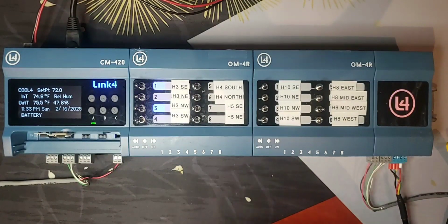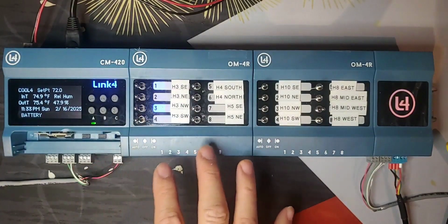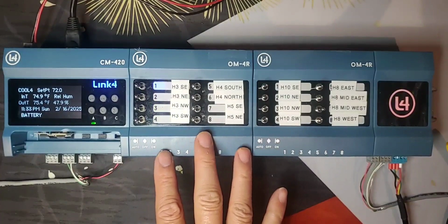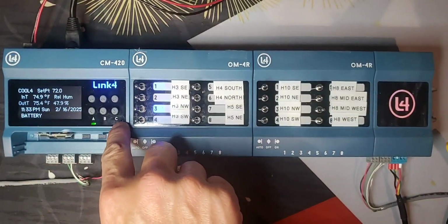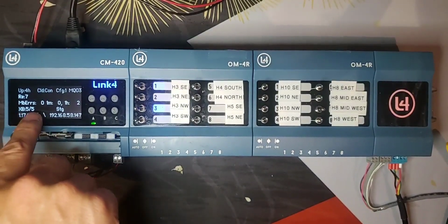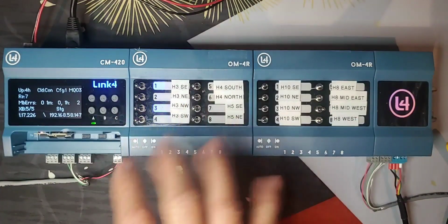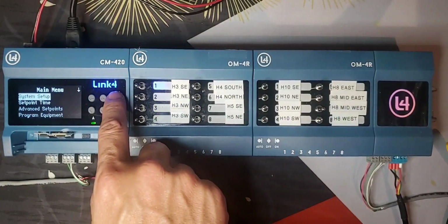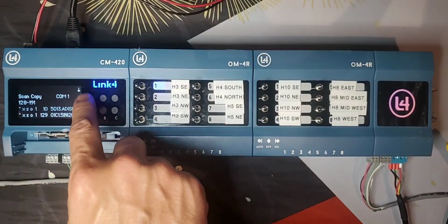So typically, if you see it go solid, that means somebody is communicating, is holding on to the line. Then the red light will be on, and you go here, and instead of 505, you would see something like 405. That means there's communication on the bus somewhere. Something is wrong. Then usually you have to go in here and rescan to see what's going on.